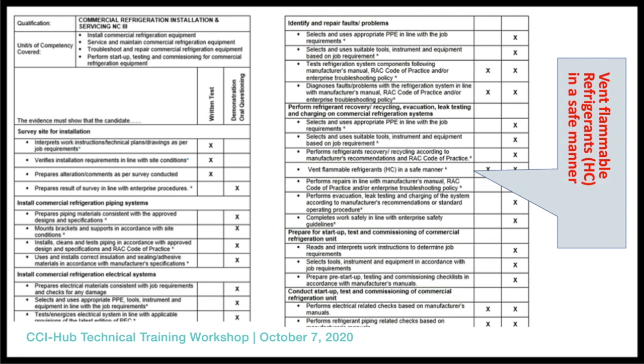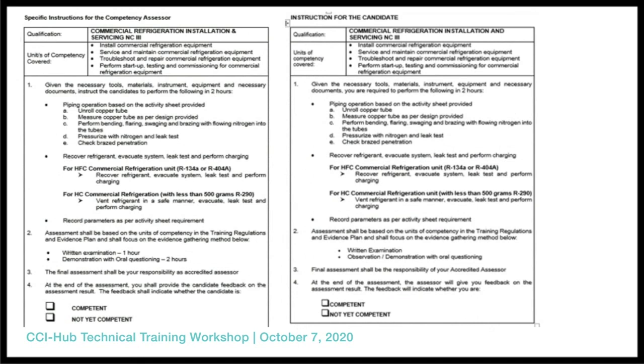Now for the flammable refrigerants, we have an activity here which says recover and recycle refrigerant. This one is for the HFC, like 134A, 404A. But if you will be dealing with flammable refrigerants, for example R290, the activity should be to vent flammable refrigerants in a safe manner. So it will be observed by the assessor how you vent flammable refrigerant like R290 in a safe manner. Everything, even the documentation and troubleshooting, is also included here.